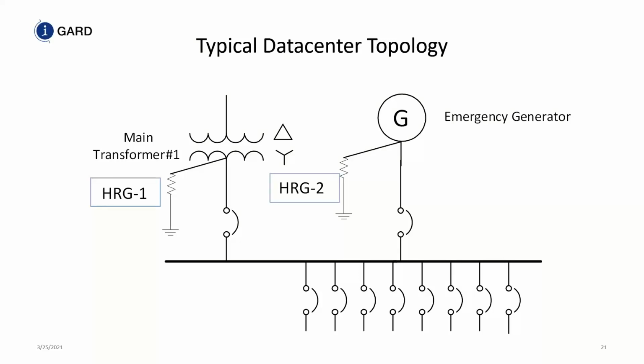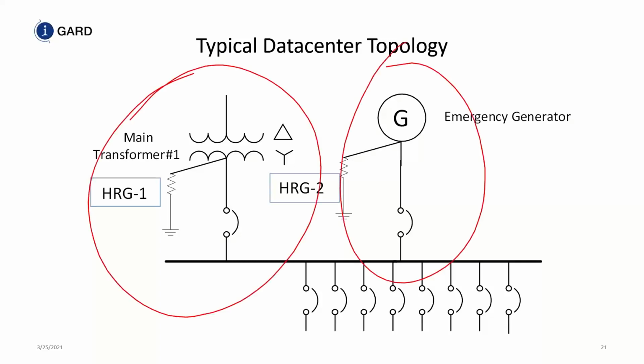So if you had a typical data center topology, and this is what I've drawn here. You've got the transformer, and you've got the generator, only one of these on at any one time. And you've got your distribution. So you need two high resistance grounding systems if you use the standard high resistance grounding topology. One for this resistor, one for this resistor. And depending on which load is on, or which source is on, that's the actual high resistance grounding system that's active at that point. The resistor will only limit the fault current when it's on the system, and this system here will tell you you have a ground fault if this breaker is closed. If this breaker is open and this breaker is closed, you have to go to this system. So you're probably looking at two different locations to determine if you have a fault on the system or not.